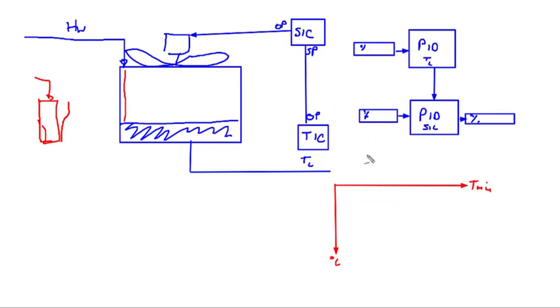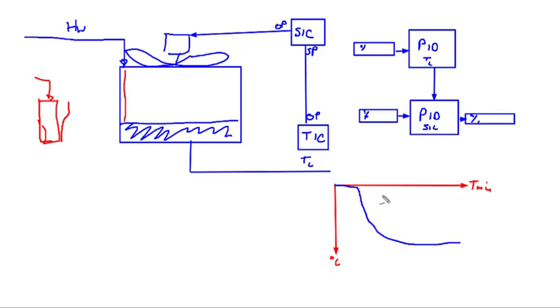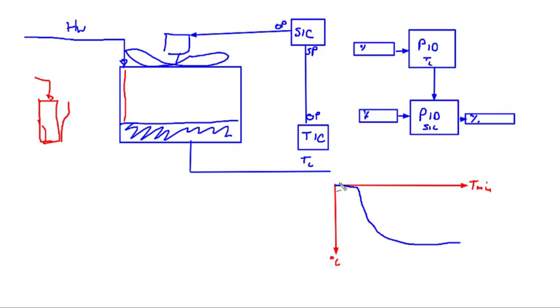What we found is that for a one percent change, there was this dead time and then the rise time which was quite quick and it settled out. There was very clean models because the operators always ran this unit in manual. The DMC plus's DMC three's model ID engine is extremely good. It's got some pre-processing which cleans up the dead time. This dead time was about 12 minutes.